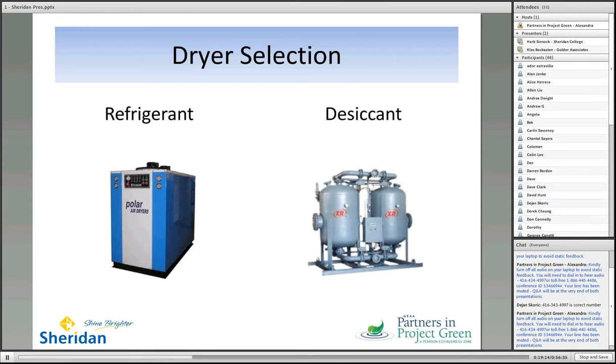Dryers are an interesting piece of the equation as well, because what we find is that in some cases, dryers are not working as intended. We went into a facility where we didn't connect the dots right away. They had a drain that was running too long on the receiver tank, and then I noticed the refrigerated dryer wasn't working. As we talked to the plant manager after our walk-around, he mentioned that at some point a few weeks previous, the receiver tank had filled half full with water. And we put the dots together. Of course, the refrigerated air dryer was not functioning properly. Instead of identifying that the refrigerated dryer was the issue for excess moisture in the system, they opened the drains more, so they actually countered with using more energy.